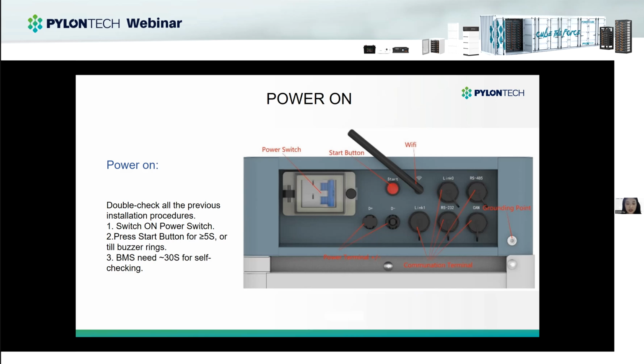And during the first time power on, the system will require a full charge process for SOC calibration purposes. And there is a tip. If you already have the ForceH1 battery system and you want to add battery modules to this existing system, first you have to fully charge the old battery modules. Make sure all the battery module voltages are the same, and then add the new battery module into the system.